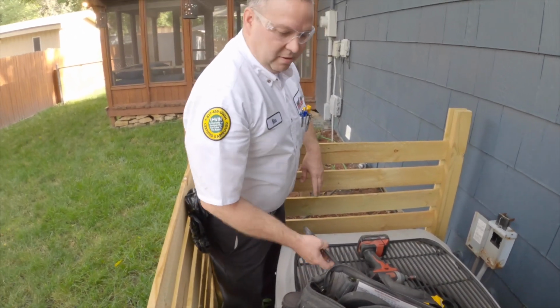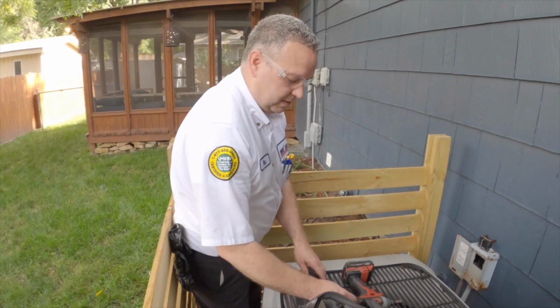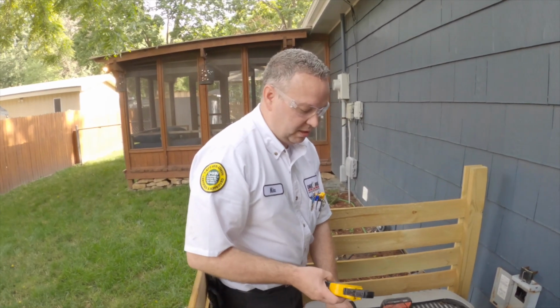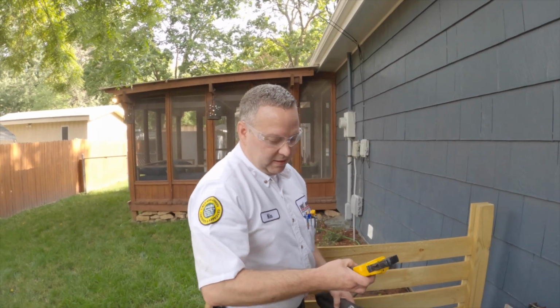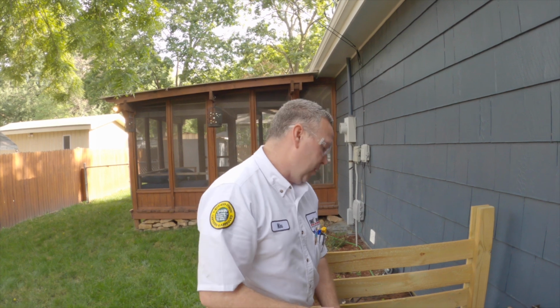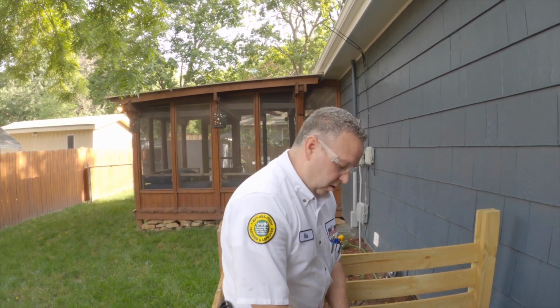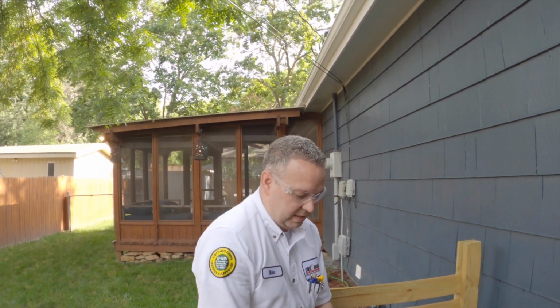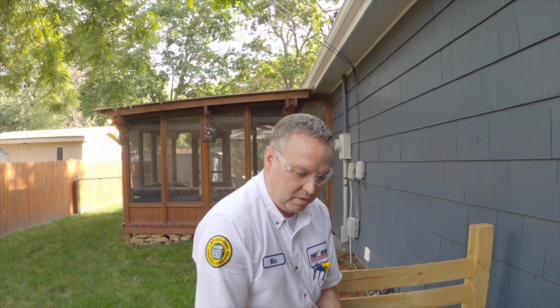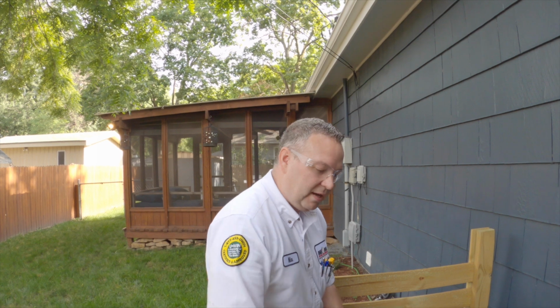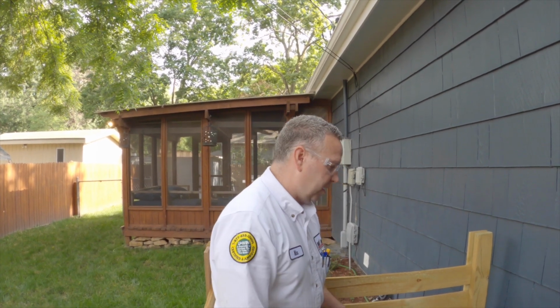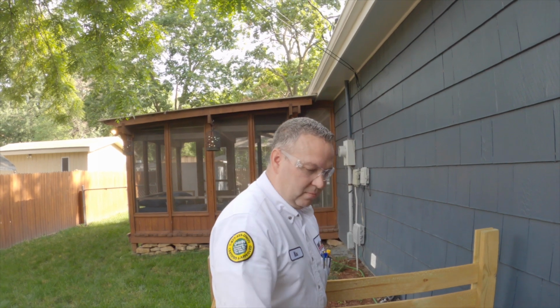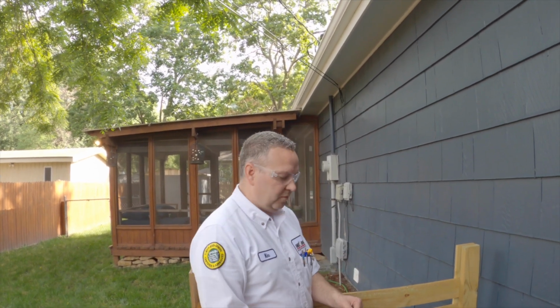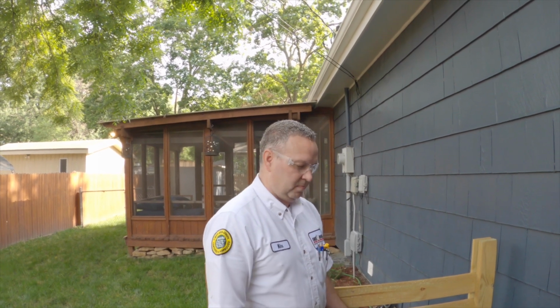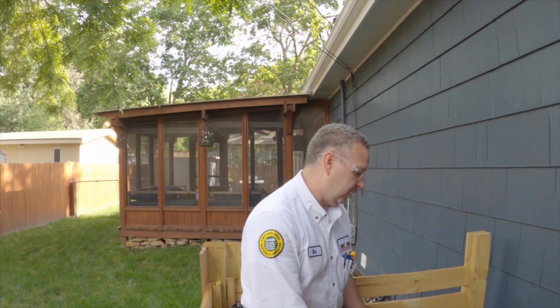The compressor, the heart of the system, has what's called LRA, locked rotor amps. You don't want it exceeding that number. If it does, it runs the potential of locking up that heart of the system. Sometimes if it gets locked up, you can get it going again. Sometimes you cannot, but when it starts running over that maximum LRA, we recommend what's called a hard start kit, which is kind of like a defibrillator for the system. The hardest part is getting that heart of the system going, and it just helps get the system going easier. Like I said, once it's locked up, sometimes you can get it going again, sometimes you cannot. But that hard start kit just helps prolong the life of things and start things easier. But yeah, they're kind of running over that maximum. Got a few things going on, but it is a 30-year-old system, so it's going to happen. Parts are going to start failing, unfortunately.